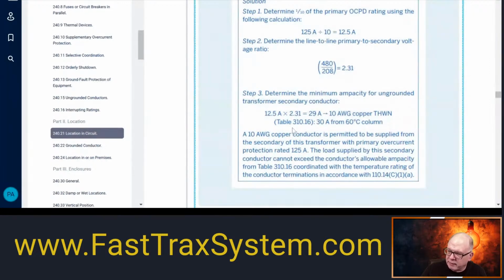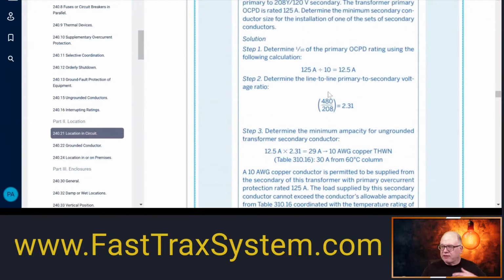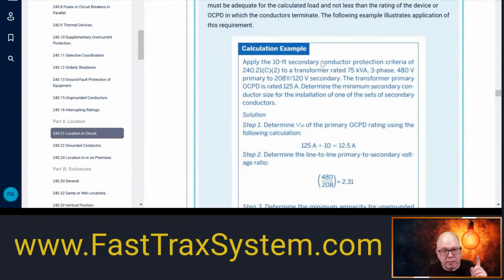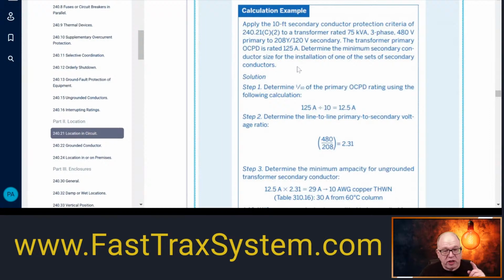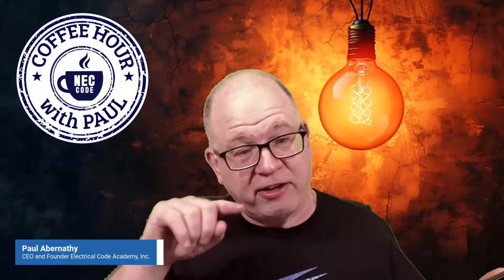If you go to Table 310.16, and again, since we weren't given any lugs here, this is a key thing to remember. We weren't given any lug information, and you might get this on an exam, and somebody will say, I can't answer this accurately. I wasn't given enough information. Yes, you were. It never said that it was 75. It never said anything about that. In fact, THWN is only rated 75. It's not rated 90 until you put the -2 on it. So there are enough factors here for people to be able to work this out and determine what the minimum size would be.